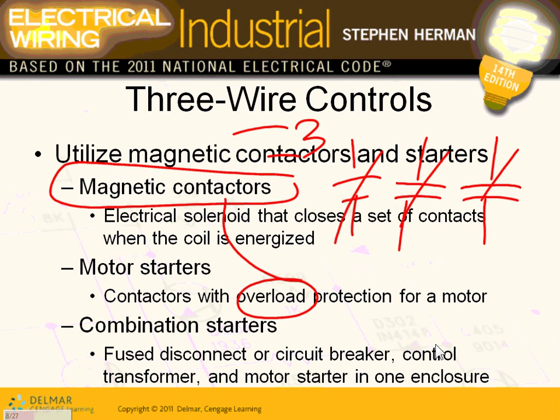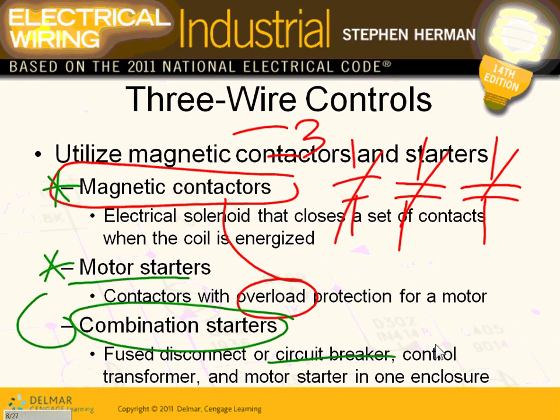This is really interesting. If I have a magnetic contactor — probably a solid-state IEC magnetic starter — and I add an overload, I've made it a starter. To make it a combination starter, I add a fuse or a circuit breaker. A combination starter includes a contactor, an overload, and an overcurrent protection device all in one box. So: contactor only, contactor plus overload equals motor starter, and contactor plus overload plus circuit breaker equals combination starter.